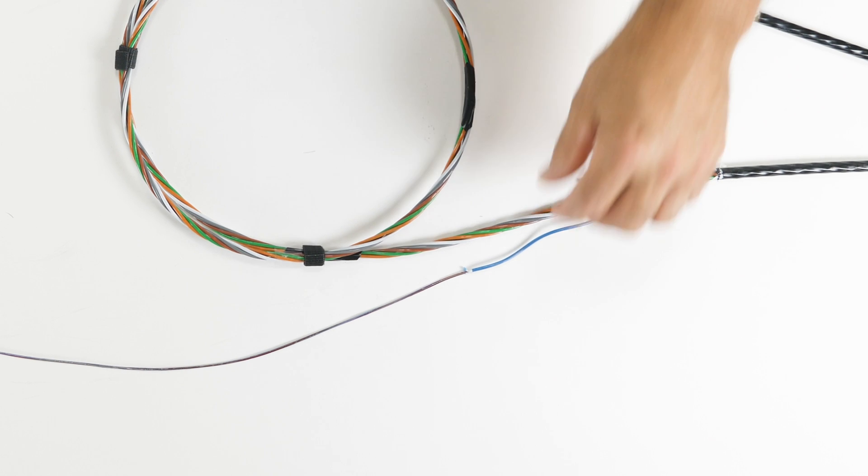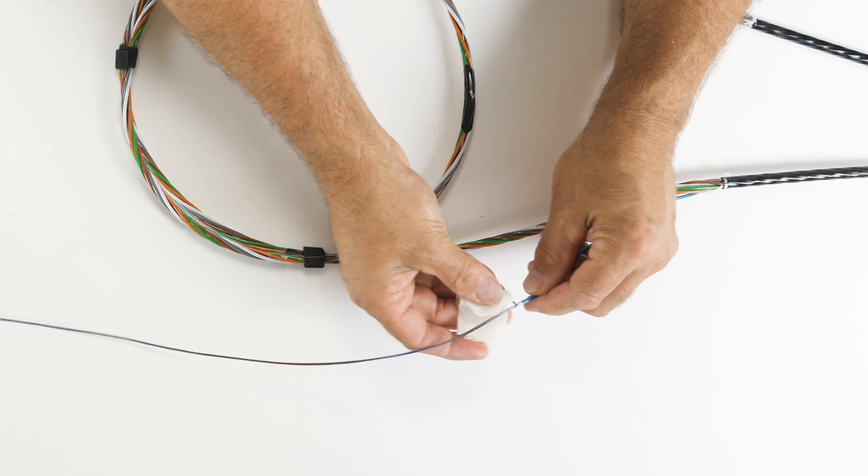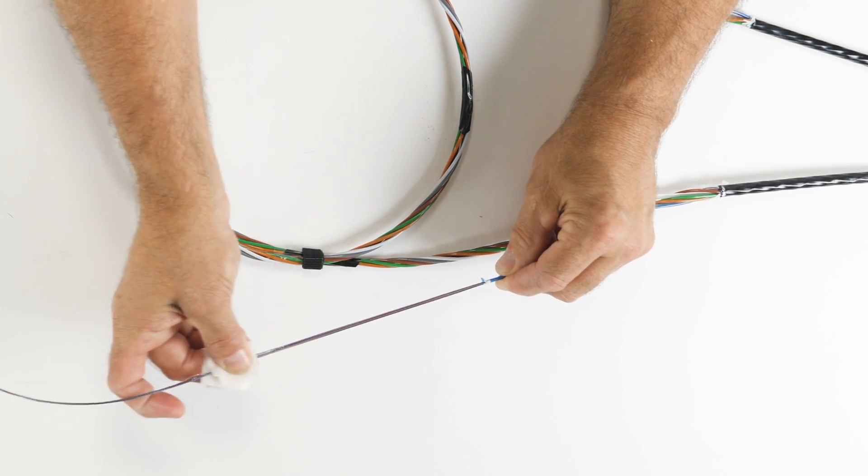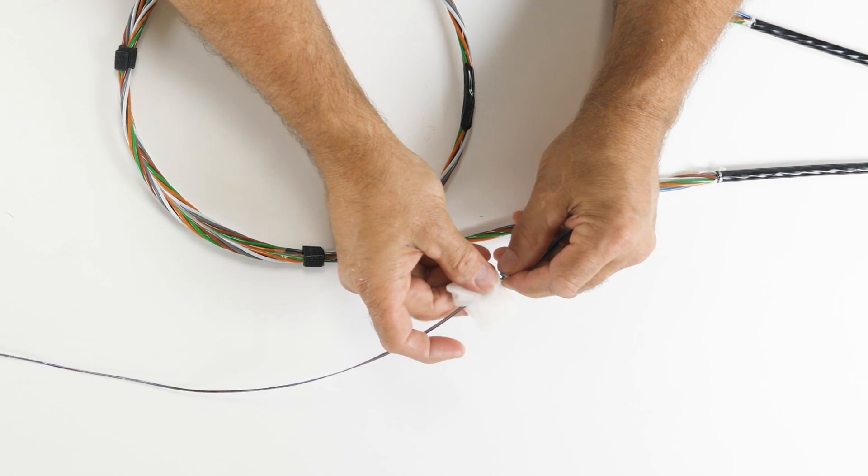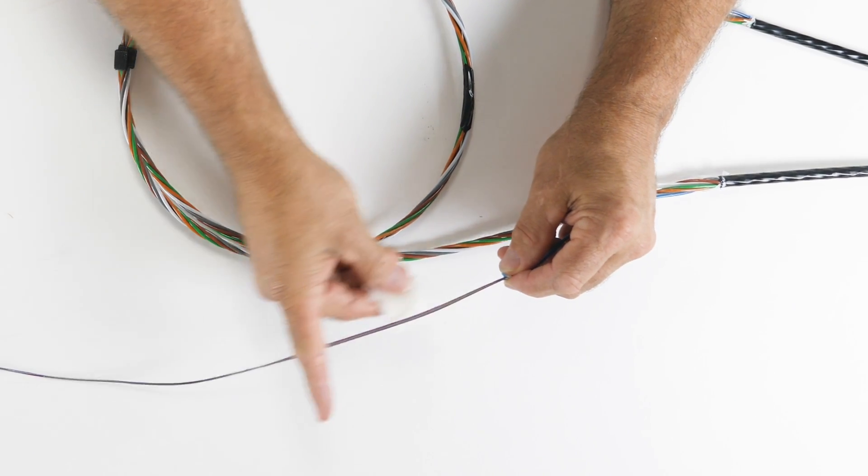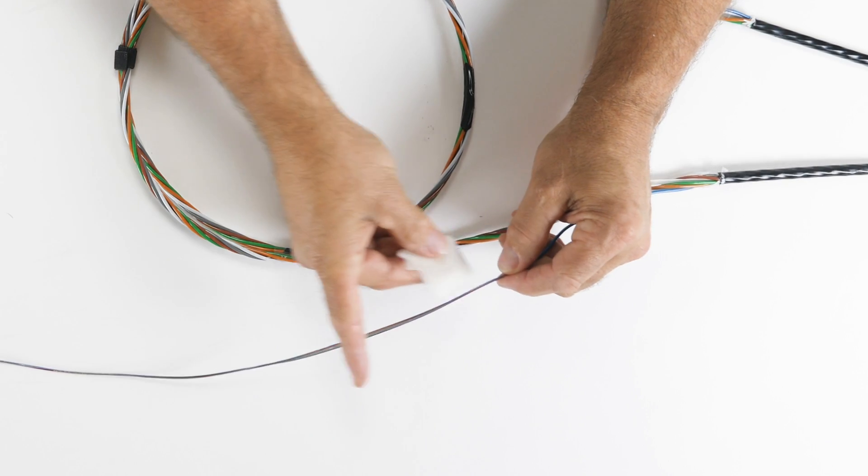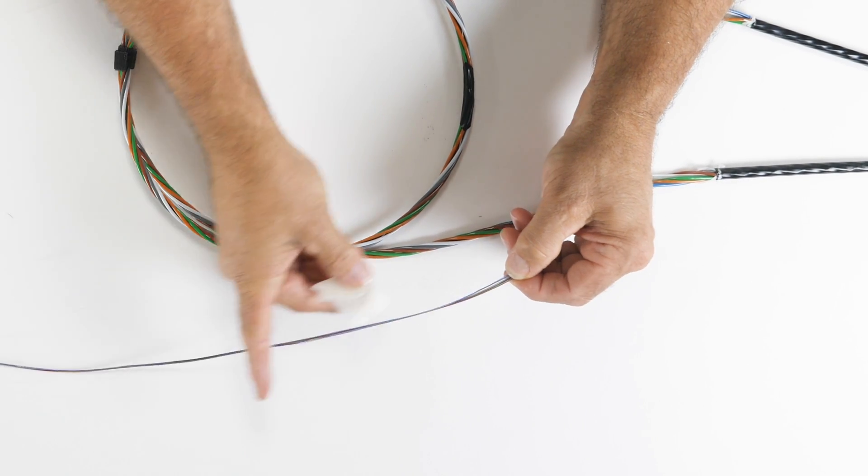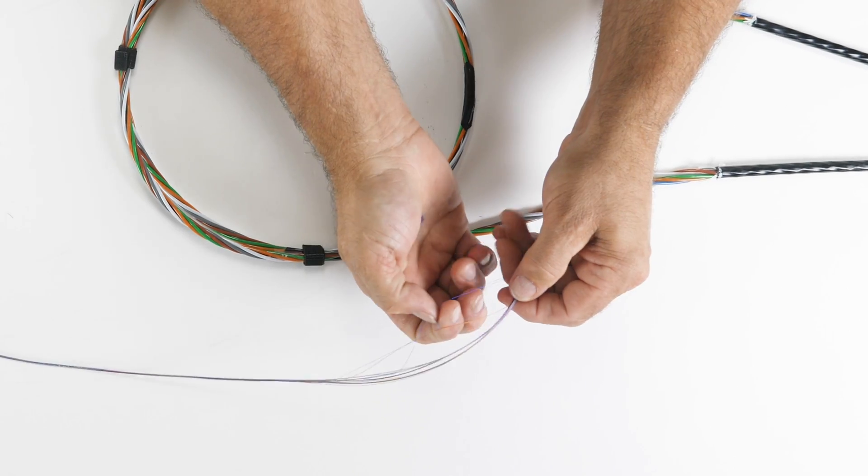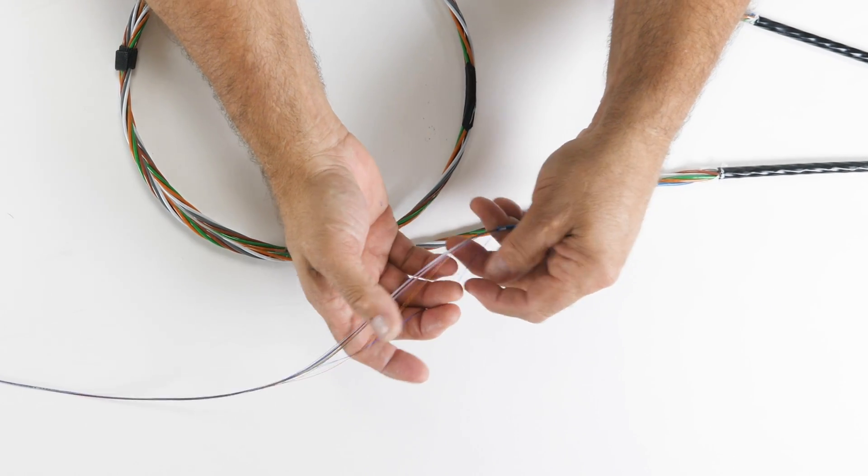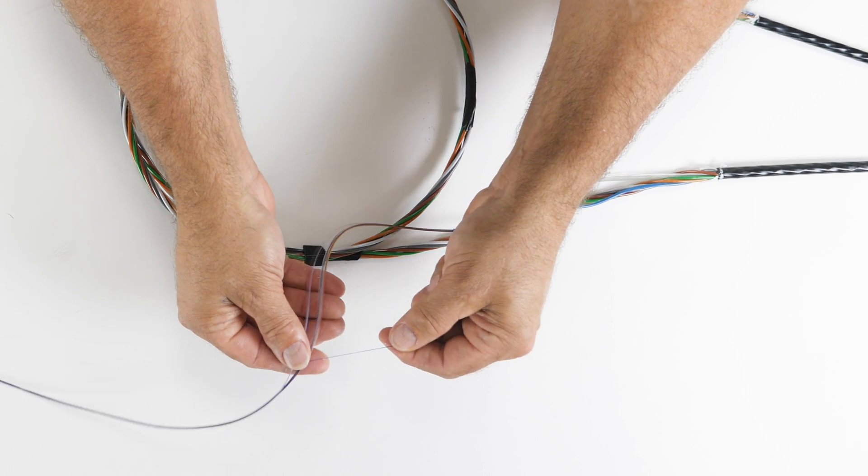In order to separate the two groups of fibers, you will need to locate the binder group inside the bundle. To perform this task, an approved fiber cleaning solution should be used to clean approximately 4 to 6 inches of all 24 fibers closest to the buffer tube. This method will expose and separate the binders for easy access. Locate both binders and slightly tug on them until you can separate each group of fibers.